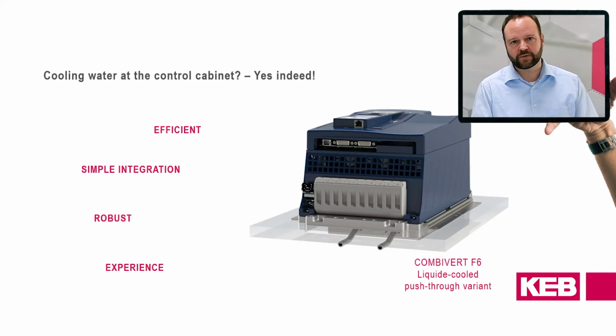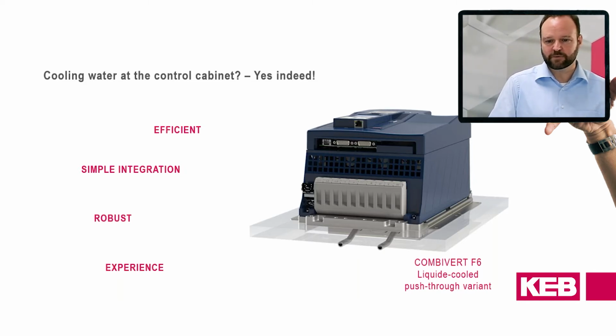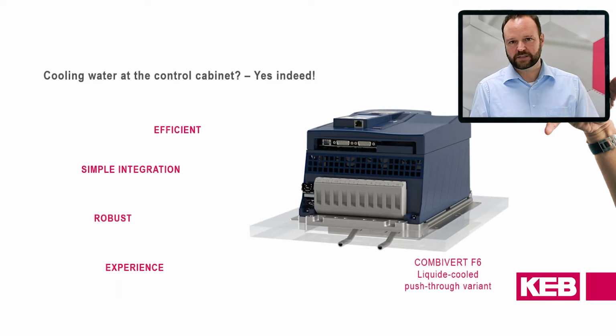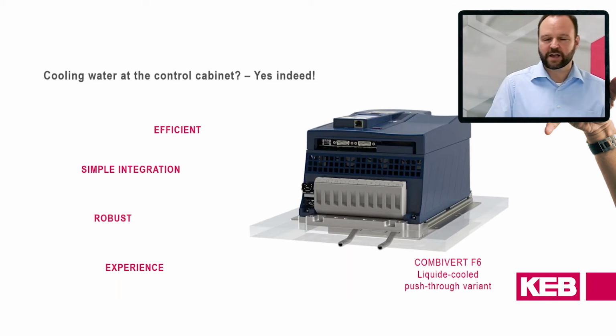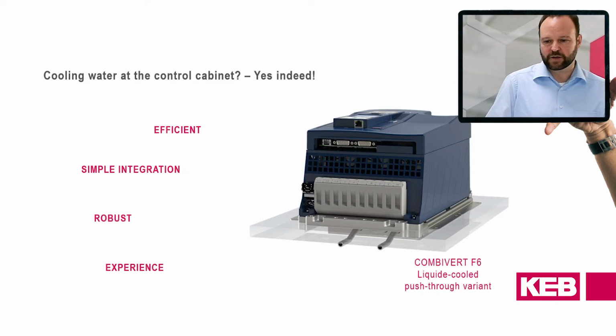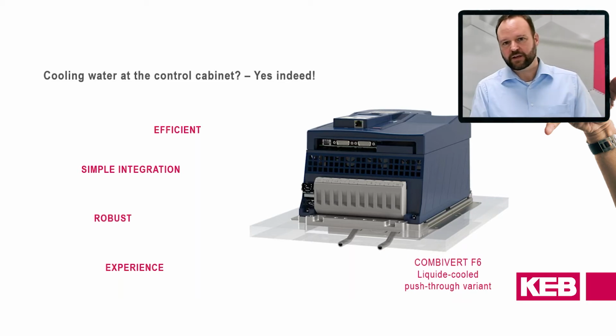So coming from the cooling to the installation possibilities, we have different kinds of installation possibilities. There's, of course, classical cabinet inbuilt IP20, but also we offer a cabinet push-through solution, which is IP54 outside of the cabinet for air and water. This is available, and in this case, approximately 80% of the losses are outside of the control cabinet, which helps to size the control cabinet smaller, and also the cooling. This is a big cost advantage if you use air conditioning in the cabinet.